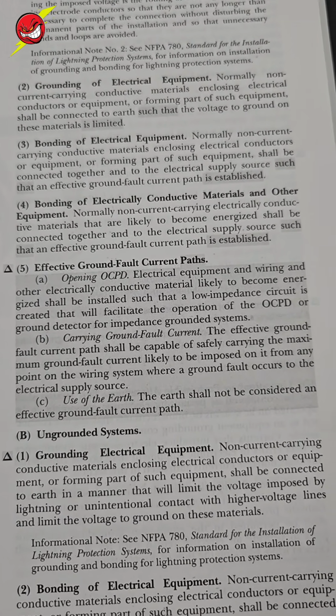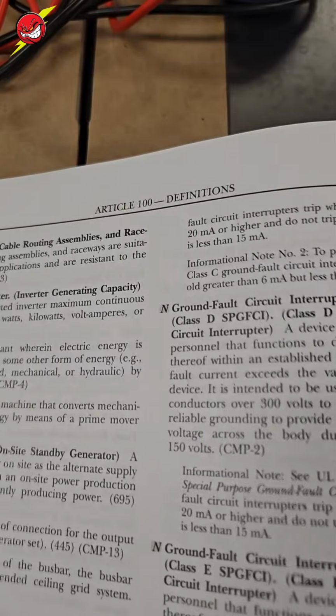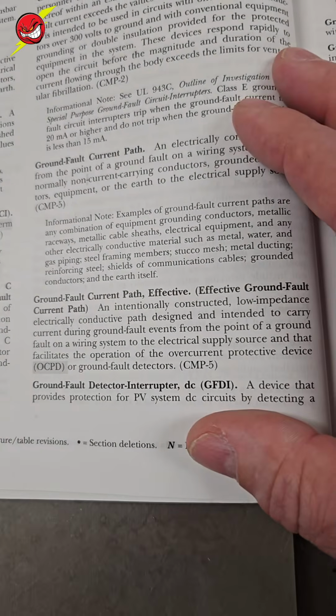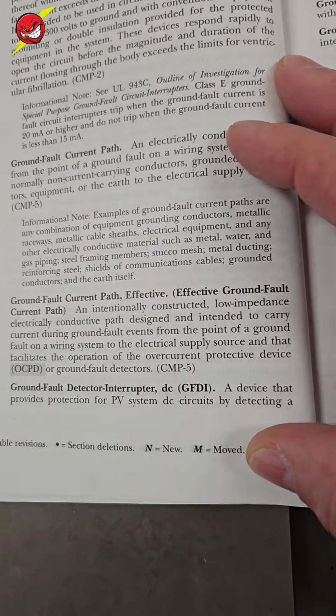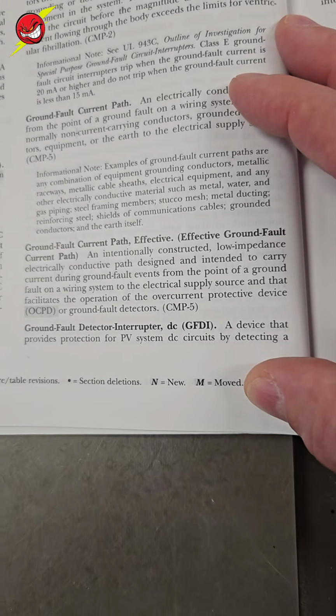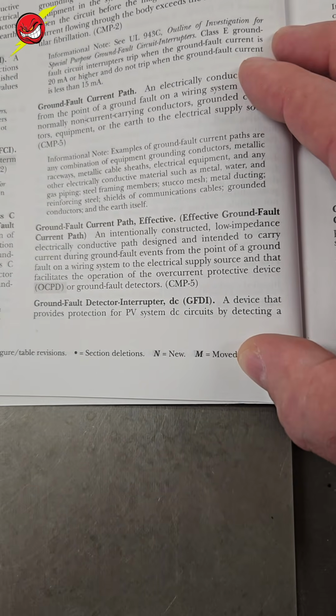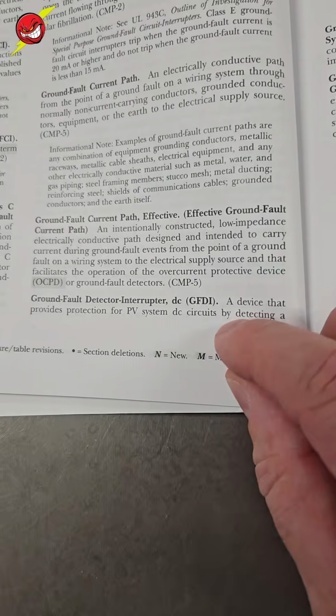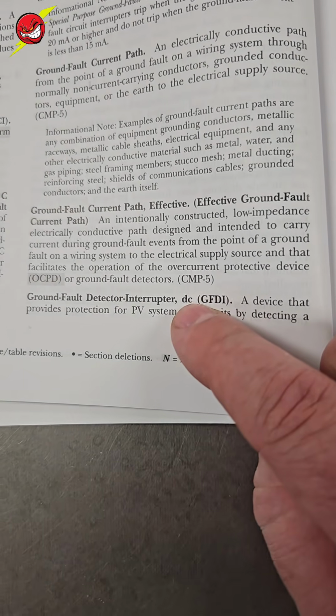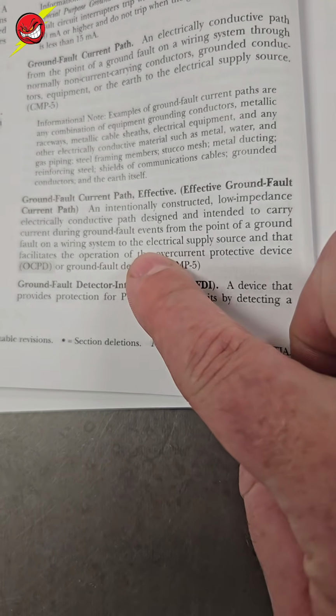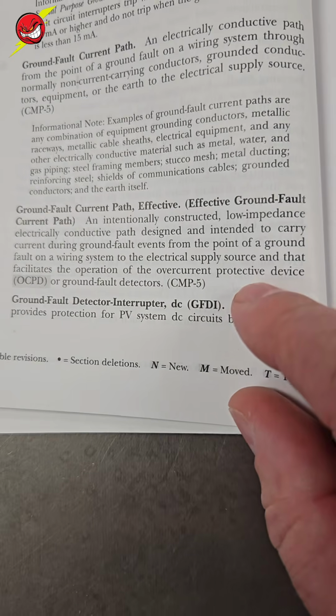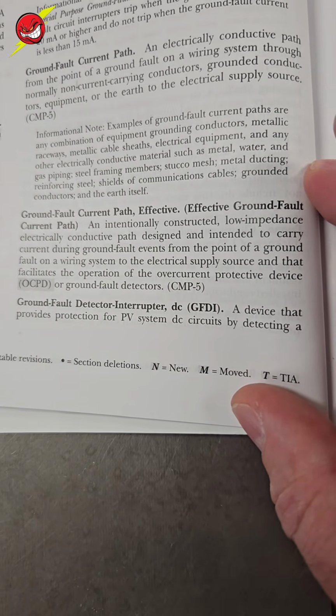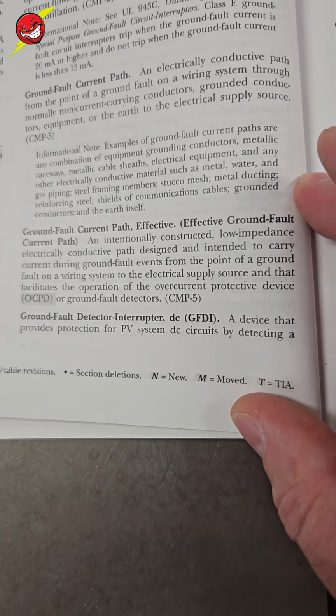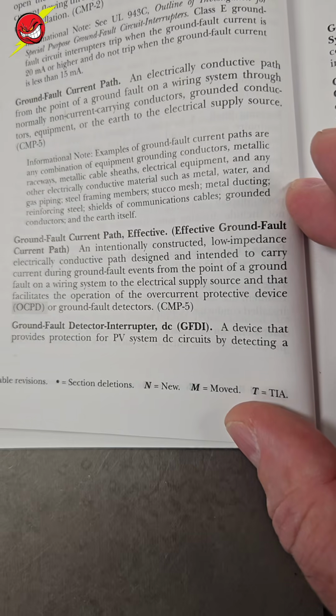Yeah, but what's an effective ground fault current path? Well, we have an entire article designated for definitions in the National Electrical Code. Here's one for effective ground fault current path. Please pause and read this whole thing. Hopefully you can read. I realize comprehension is a struggle for some of you. But it literally states that if there is a fault, it needs to go to the electrical supply source. Not to earth, not to ground, not to wherever. It needs to go back to the source.